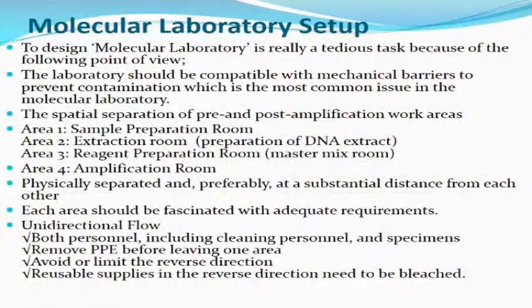It shouldn't be done in the extraction room, to avoid contamination. Also, the amplification room should be a different setting, a different room, a different place within the molecular laboratory. There must be physical separation, and preferably at a substantial distance from each other. Each area should be furnished with adequate requirements. There must be unidirectional flow. Where you start from, you must not go back there. You must flow until you get to the last place. If not, there could be contamination.